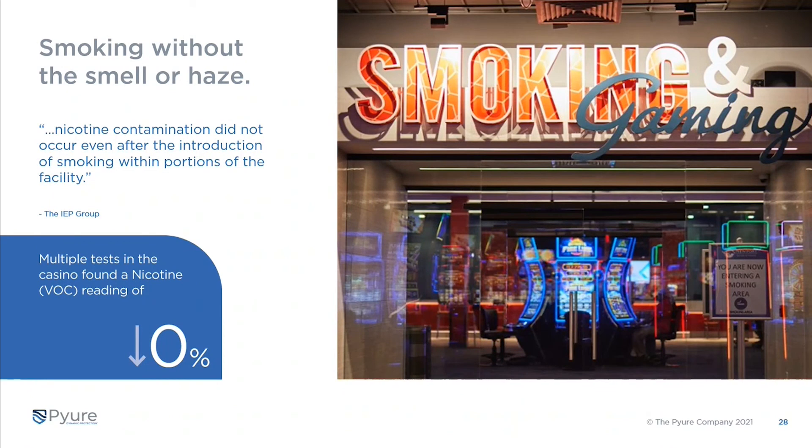Regarding smoking — the criteria Churchill Downs was initially using with Pyure had to do with smoke, as the casinos are smoking environments. Directly from the third-party testing agency report: nicotine contamination did not occur even after the introduction of smoking within portions of the facility. When they did the after-sampling at normal capacity, they detected zero percent nicotine across multiple tests in the casino — very impactful results for that particular VOC.